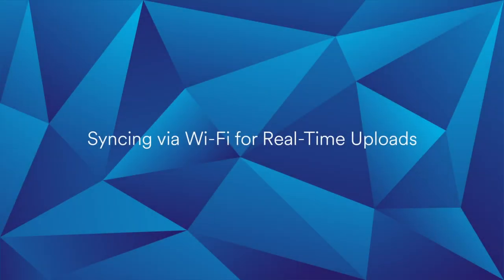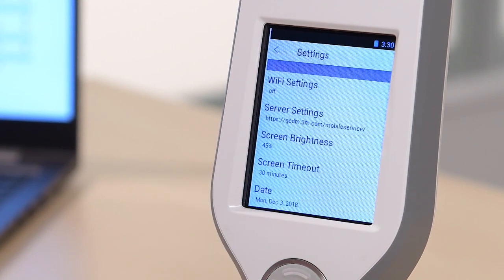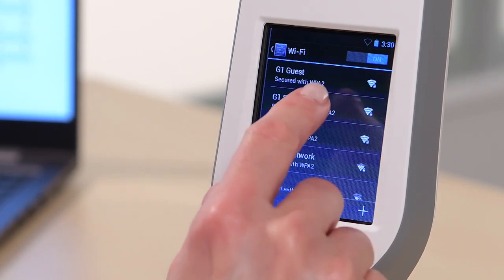Once you have registered your Luminometer, you can set up Wi-Fi to automatically upload results to QCDM and automatically download your monitoring plan from QCDM to the Luminometer. Tap the hamburger menu in the upper right-hand corner of the screen. Tap Settings, then tap Wi-Fi Settings, and then turn on Wi-Fi by changing the indicator from off to on. Select the appropriate Wi-Fi network and enter security credentials if required. To prevent mistakes in entering the password, it's a good idea to scroll to the bottom of the screen and check the box to Show Password.